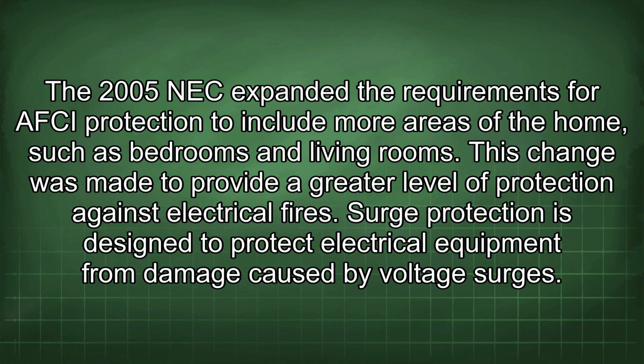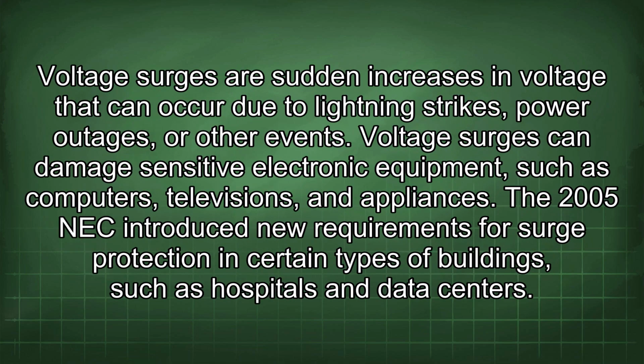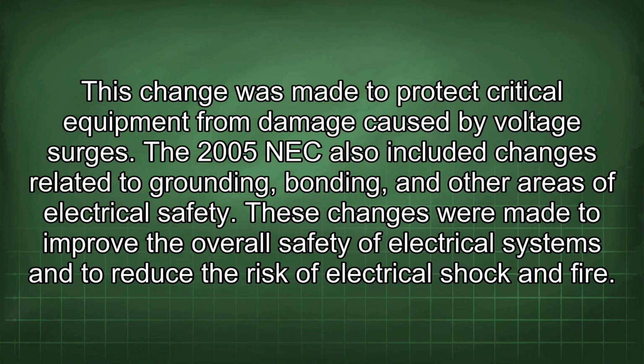Surge protection is designed to protect electrical equipment from damage caused by voltage surges. Voltage surges are sudden increases in voltage that can occur due to lightning strikes, power outages, or other events. Voltage surges can damage sensitive electronic equipment such as computers, televisions, and appliances. The 2005 NEC introduced new requirements for surge protection in certain types of buildings, such as hospitals and data centers. This change was made to protect critical equipment from damage caused by voltage surges.